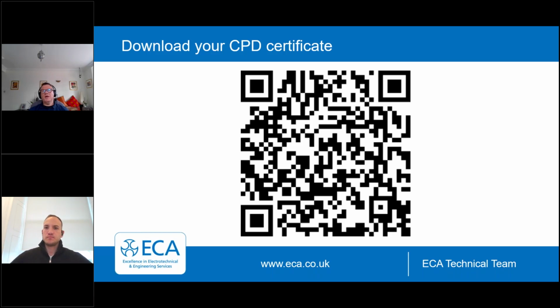It depends. If it's a like-for-like maintenance, then I would suggest that you're not necessarily changing anything. You may wish to just confirm, and then maybe manufacturer's data would go with a maintenance. It's sort of akin to a 7671, isn't it? If you are just updating socket outlets or replacing something that's worn out. But if you're changing design parameters, then I would suggest we're back to the model forms in 5266.